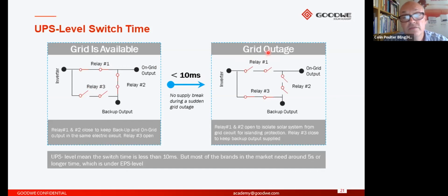When there is a grid outage, and this obviously can happen, then within 10 milliseconds, relay 1 and relay 2 open and relay 3 closes. So there is now no direct connection between the backup output port of the inverter and the on-grid supply of the inverter, so no power can get back into the grid. So we maintain the anti-islanding requirement. And as I said, we do refer to this as a UPS level switchover time, and it's quite seamless.